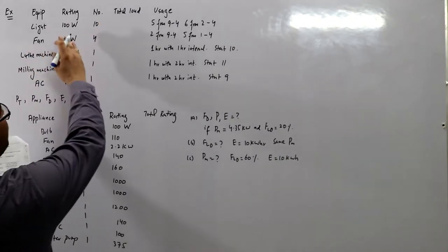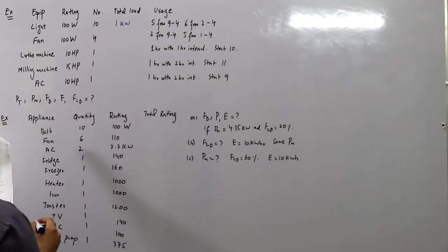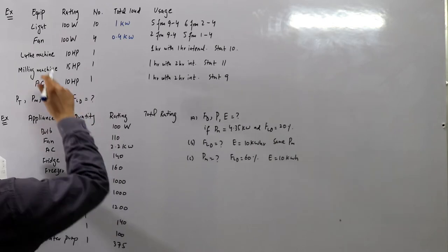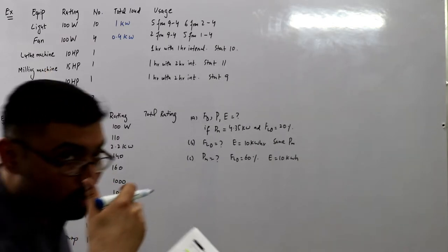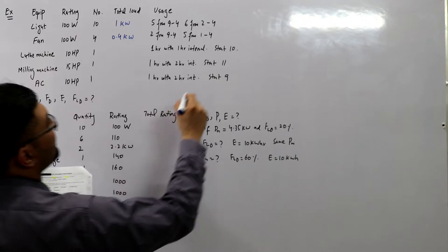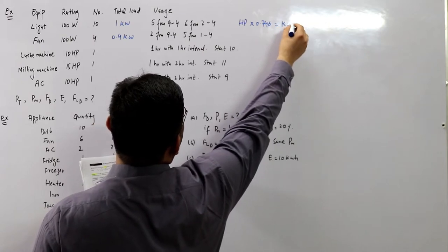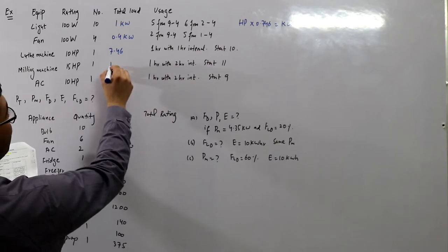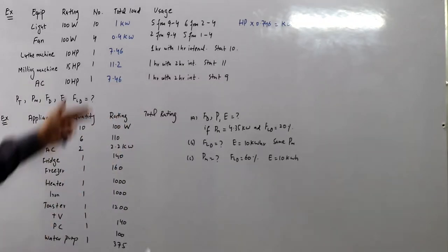You can find the total load of each: 10 multiplied by 100 would be 1000 watts, which is 1 kilowatt. Similarly, 4 multiplied by 100 would be 400 watts or 0.4 kilowatts. For the horsepower values, multiply by 0.746 to convert to kilowatts. So 10 × 0.746 = 7.46 kW, 15 × 0.746 = 11.2 kW, and 10 × 0.746 = 7.46 kW.